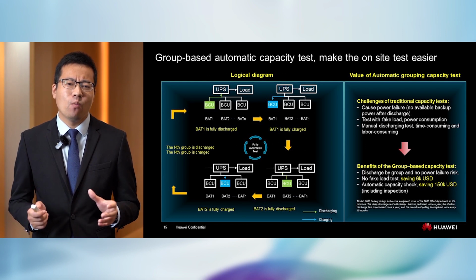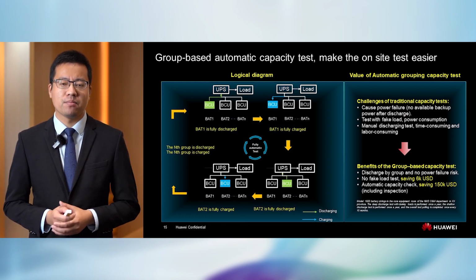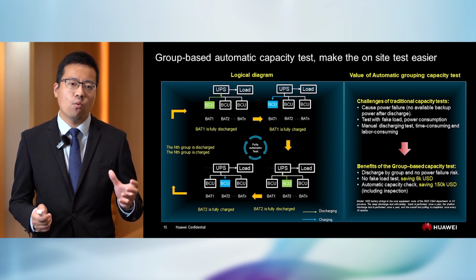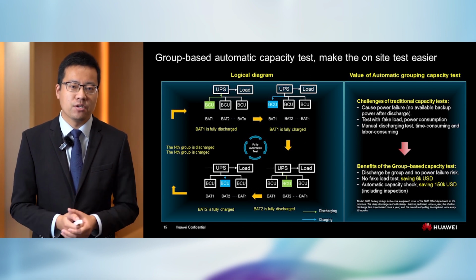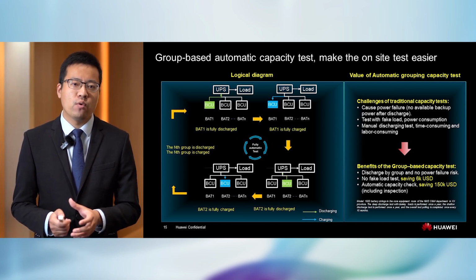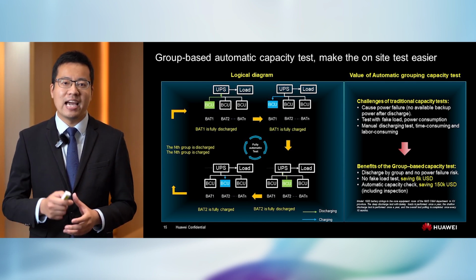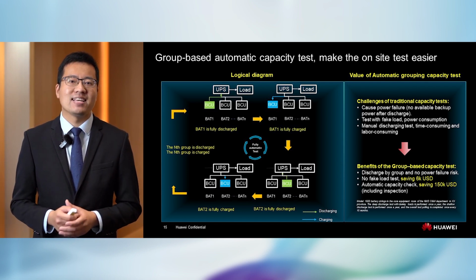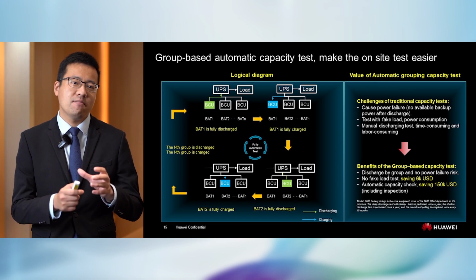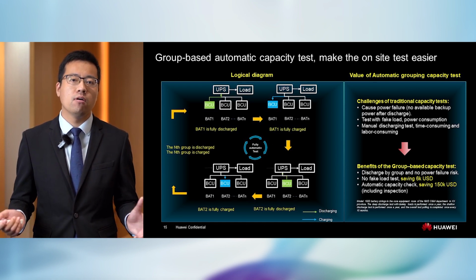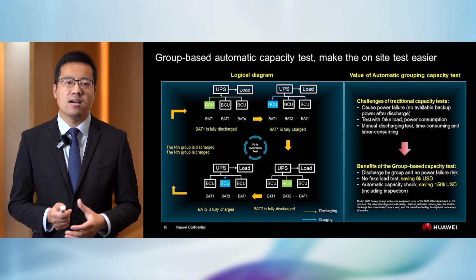Another way we are improving is the testing of capacity. We know that when the battery is getting older, we need to test the capacity. But normally we have to rent a fake load, reconnect the cables, then charge and discharge the battery as a whole. It has a failure risk when the power is off and the battery is empty, because there is no power. So we have this group-based automatic capacity testing. It has the benefit that, firstly, at any time only one cabinet is empty. So even if the power fails at this time, there is no risk for the IT load.